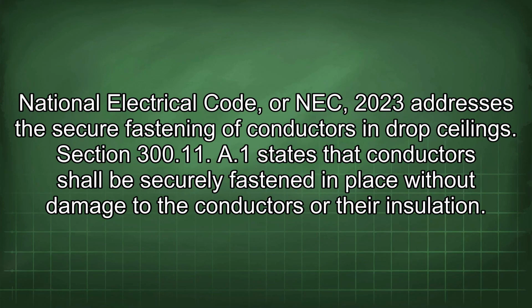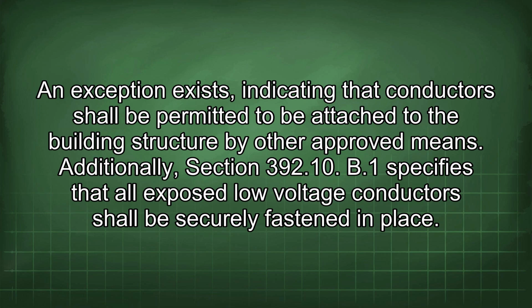National Electrical Code, or NEC, 2023 addresses the secure fastening of conductors in drop ceilings. Section 300.11.A.1 states the conductors shall be securely fastened in place without damage to the conductors or their insulation. An exception exists, indicating that conductors shall be permitted to be attached to the building structure by other approved means.